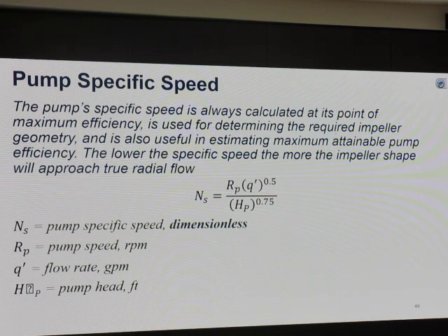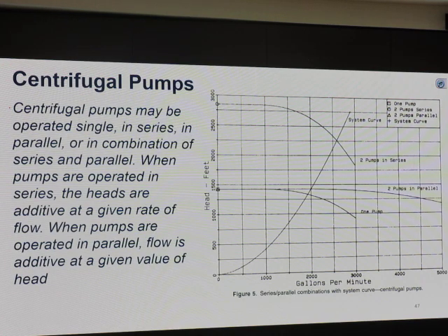All right, this slide that talks about the pump speed, we skip that, and we will have it for that level. Centrifugal pump, put it in series, put it in parallel. I made the correction on this slide. It says centrifugal pumps will be operated singly, in series, in parallel, or in combination. When pumps are operated in series, the heads are additive at a given rate. When pumps are operated in parallel, the flow is additive.